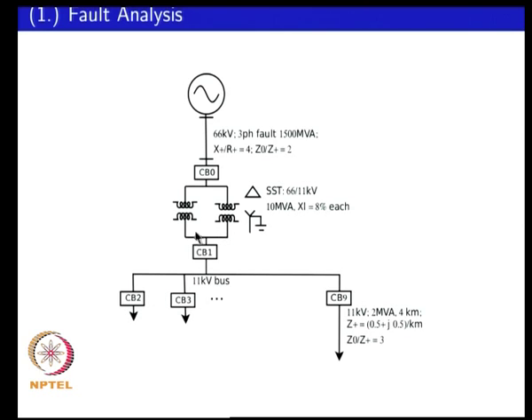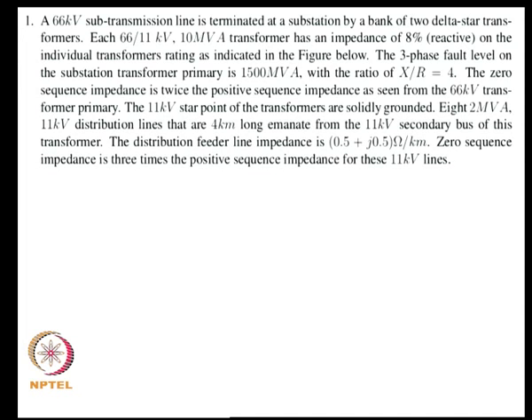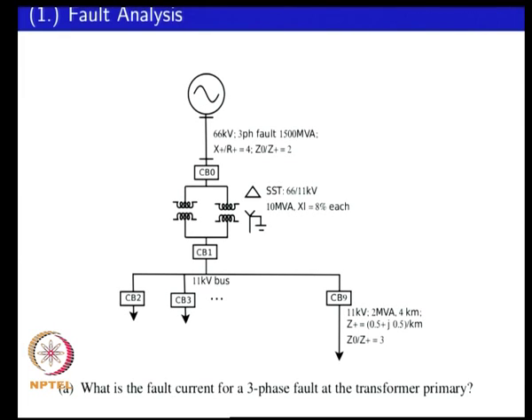The outputs of the transformers combine to form the low-voltage bus at the substation, and you have 8 feeders radiating out from the substation. Each feeder is rated at 2 MVA at 11 kV. The first problem is to determine what is the fault current for a three-phase fault at the transformer primary.